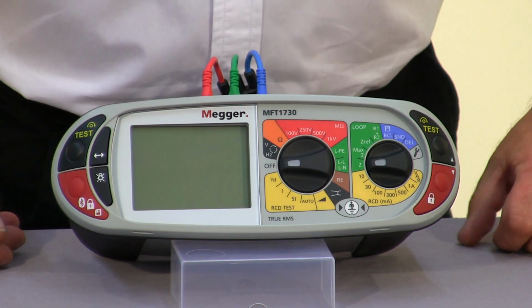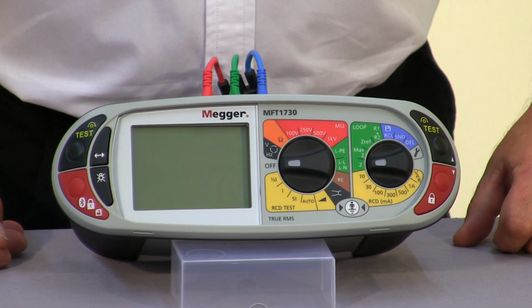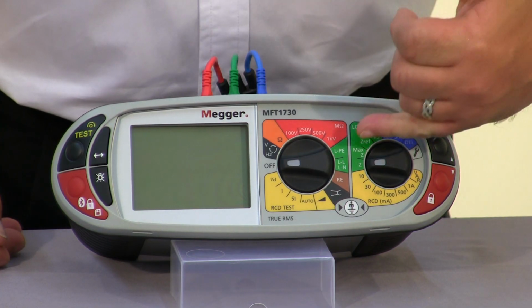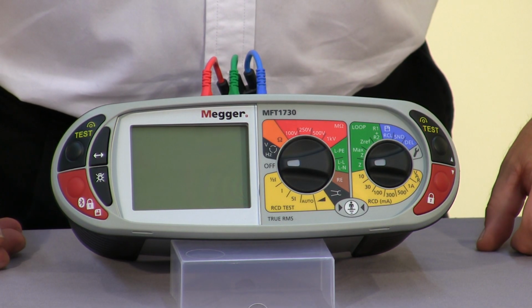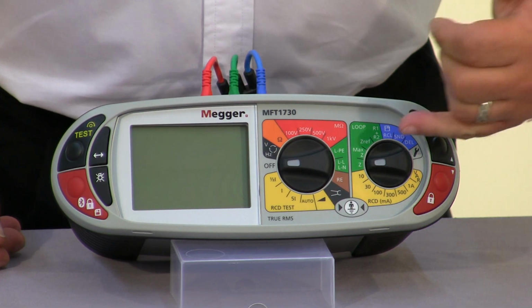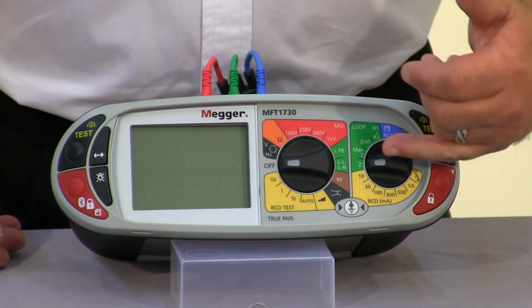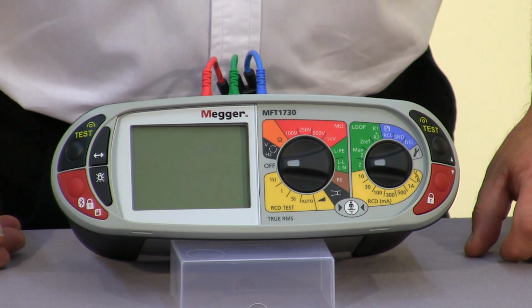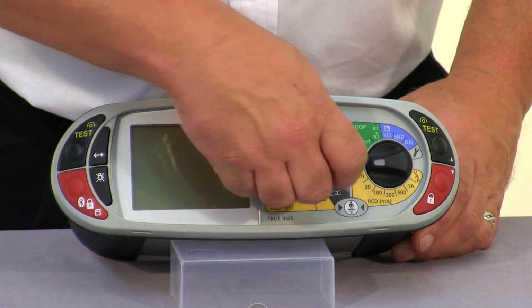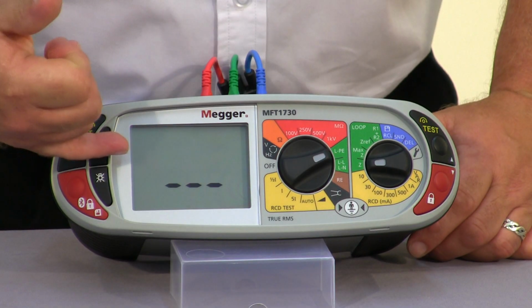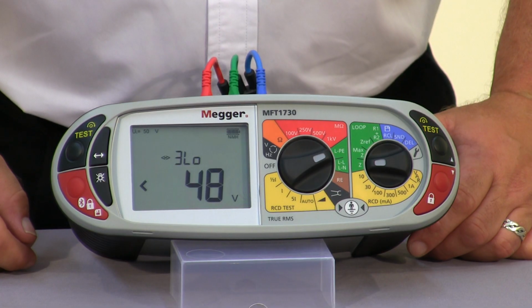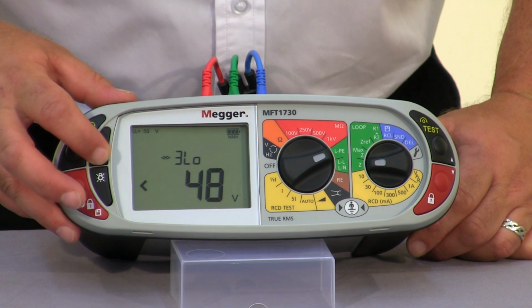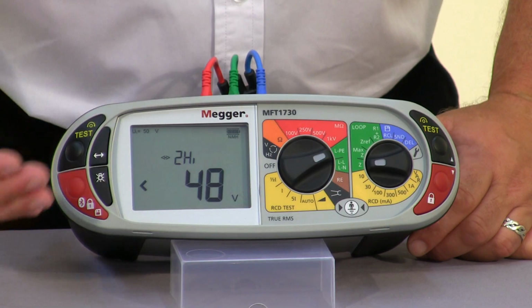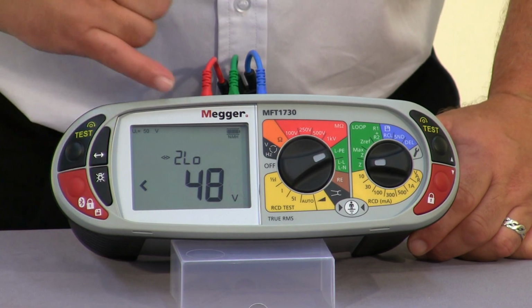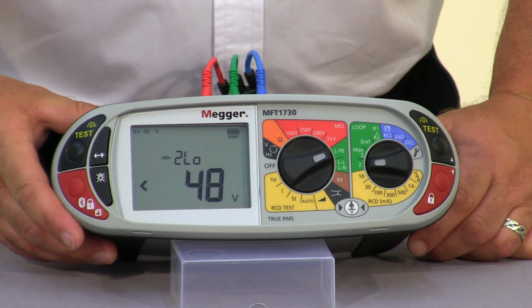Okay, so let's look at the earth loop impedance test features of the MFT1700 series. As you can see on the range selection knob, we have our LPE or our LLLN position, and over on the right hand side we have a standard Z measurement as well as some ancillary tests, which I'll talk about shortly. So selecting our LPE, you'll notice on the top of the display the unit has defaulted to a three-wire no-trip test, and we can actually cycle through using the function button to a two-wire high current test, or alternatively the patented two-wire no-trip test.